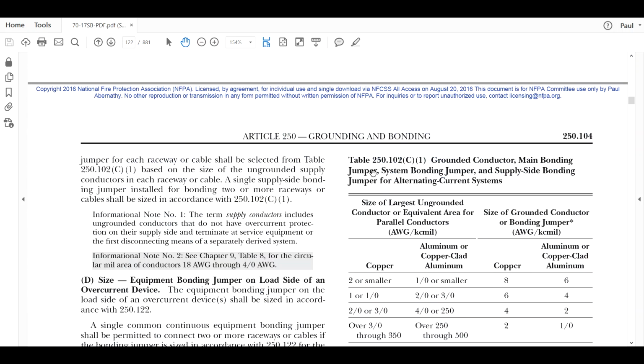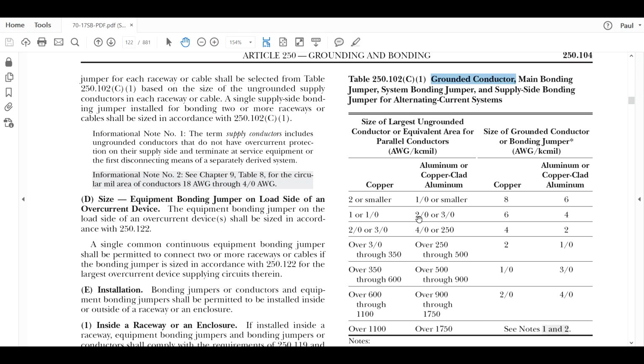So here's the table right here. This table does grounded conductor minimum sizing, main bonding jumper, system bonding jumper, and supply side bonding jumper, all of that is good right here. Of course, we are going to use it for our system bonding jumper sizing and for our supply side jumper sizing. In the next video, we'll talk about the grounded conductor sizing and some of the rules, and I'll show you the formula to size them based on the unbalanced load and all that. But right now, this is what this table is all about.